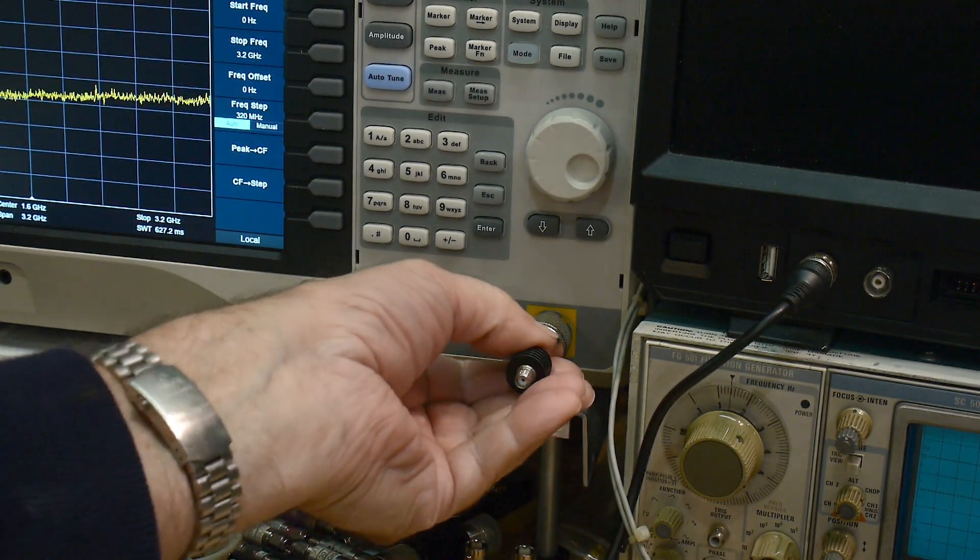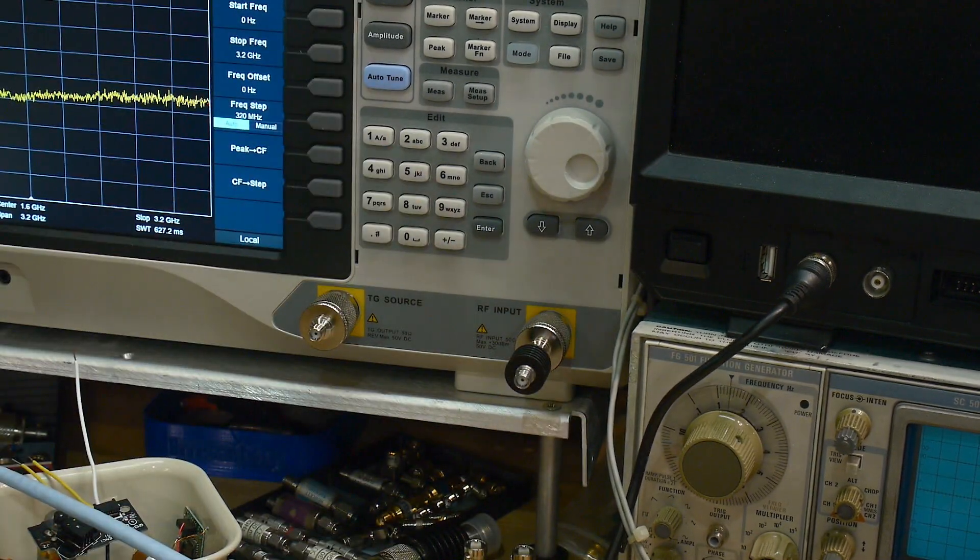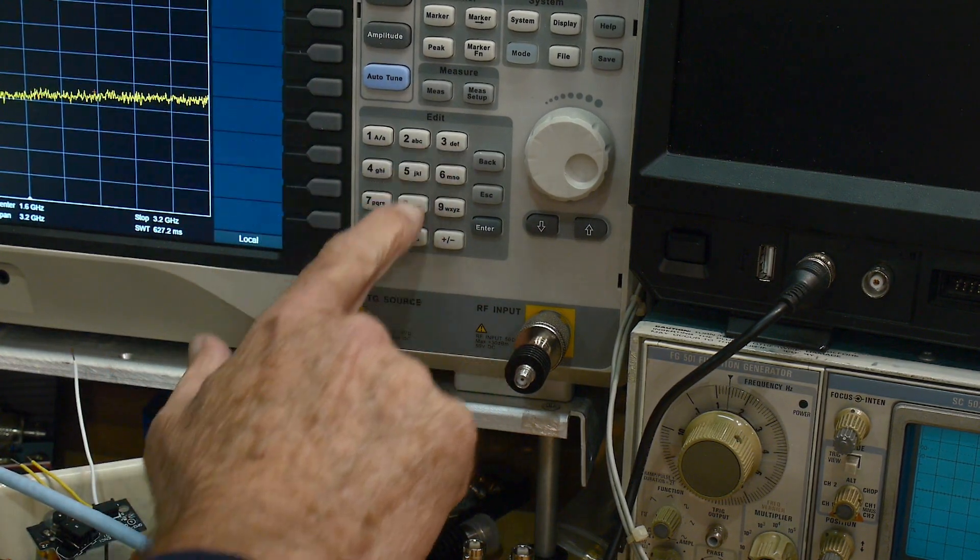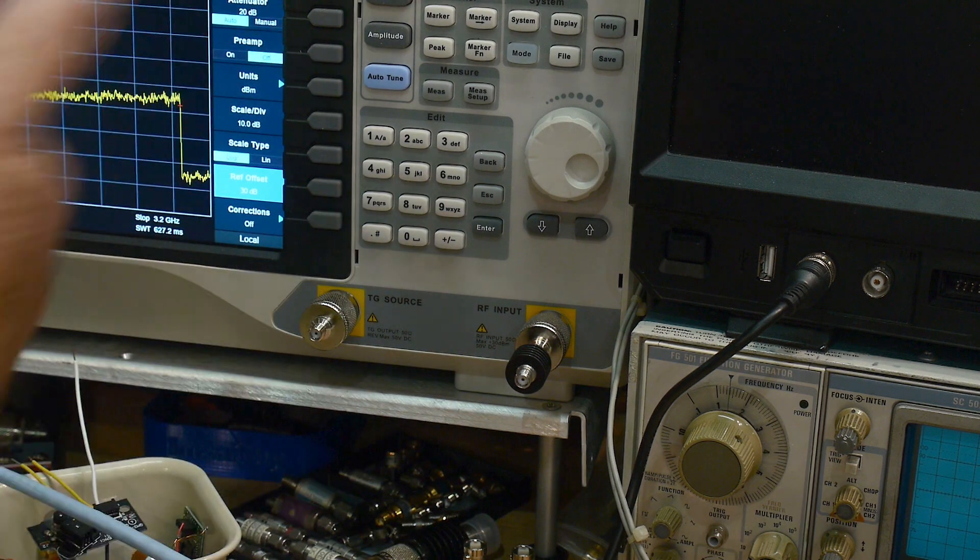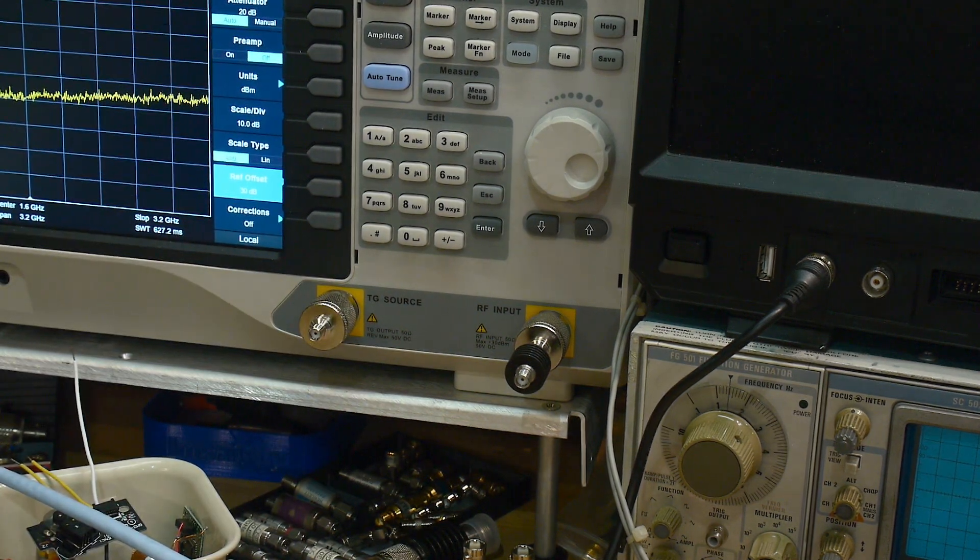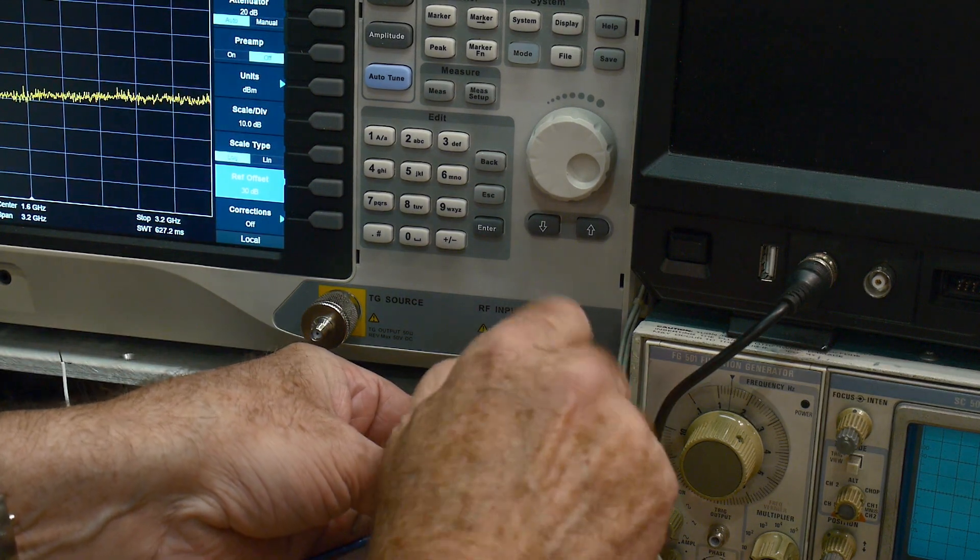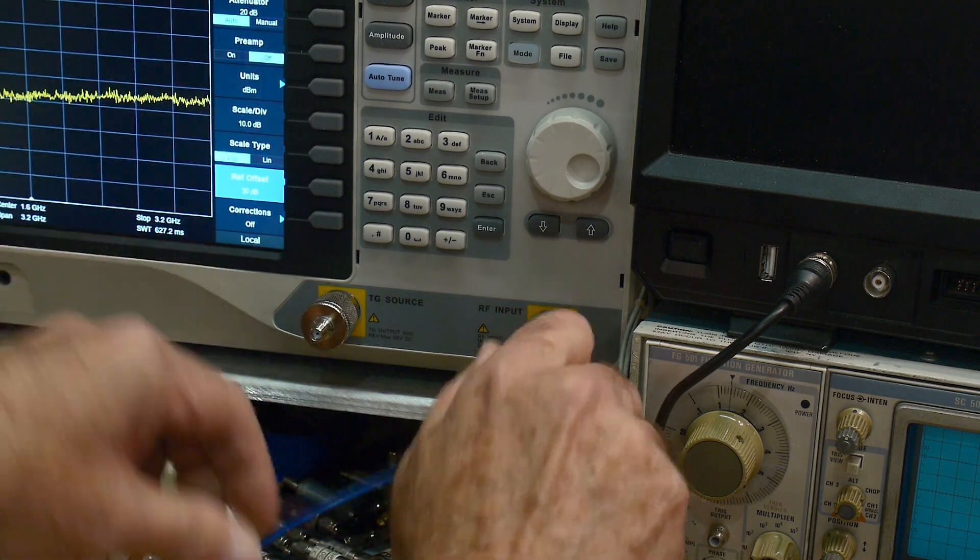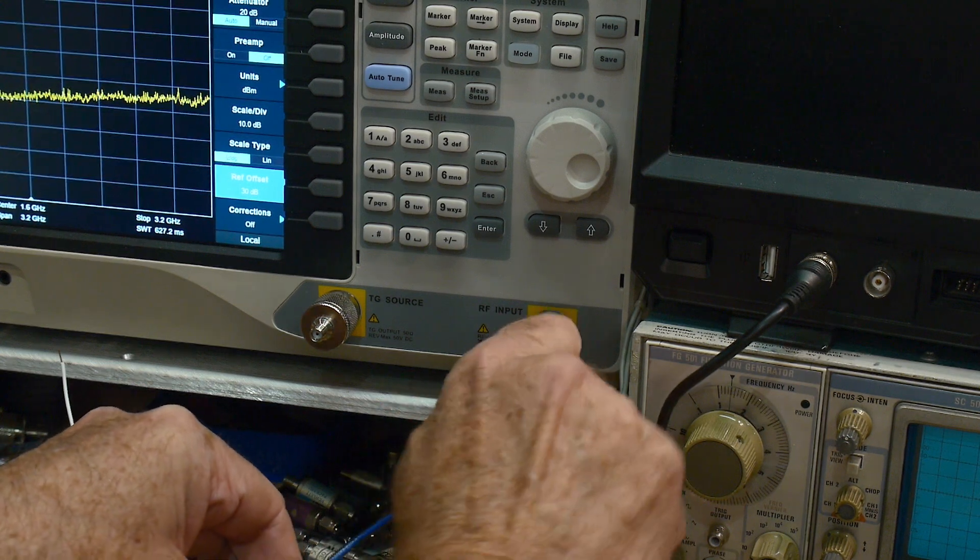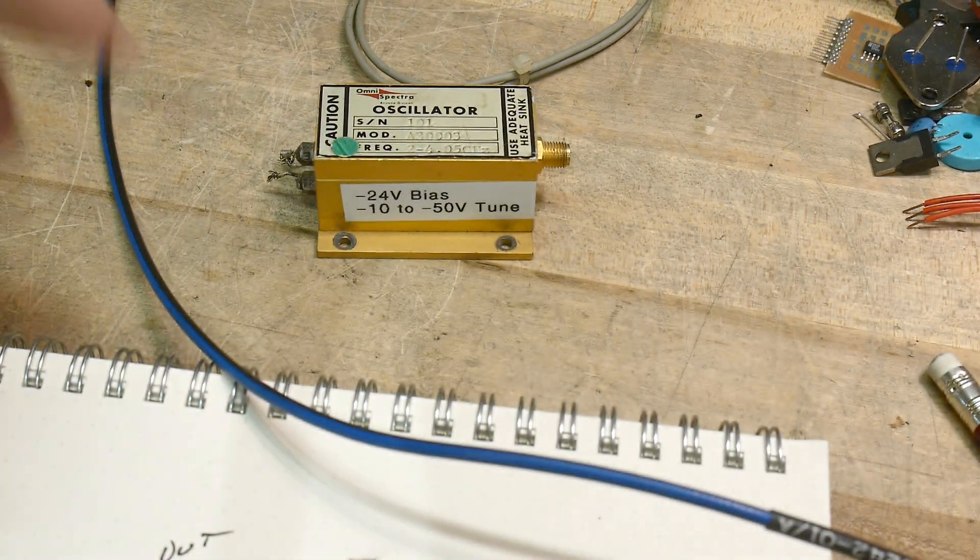So what I'm going to do is I'm going to put a 30 dB attenuator here. So, we have to tell the instrument that we have a 30 dB attenuator in line so it can do the math correctly. And then we will hook up our cable. And now we can go back down over here, hook up our cable to the oscillator.